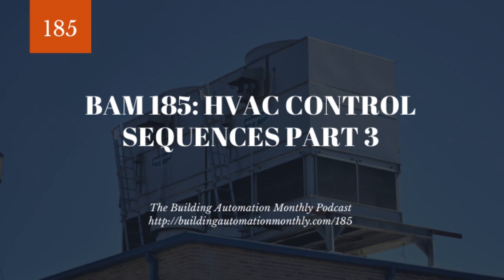All right, so with that being said, that kind of takes us through this constant air volume air handler. Let's now look at the variable air volume, because there's really not too much different, and I think we have enough time. We're at 24 minutes. The real big difference of a variable air volume system is utilizing a VSD or VFD. A VSD varies the speed of the fan, whereas a VFD varies the frequency of the electrical signal, and that's how it controls the speed of the fan.